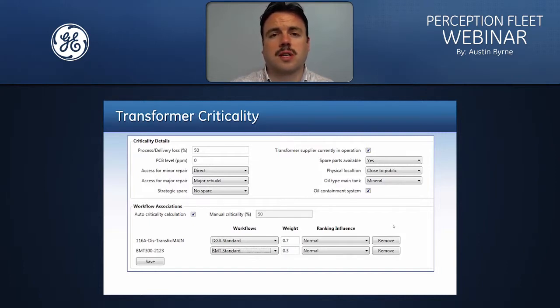So for example, if an asset is close to public and access for major repair is major rebuild, then that directly impacts the risk index categorization for that asset because it is seen as being at higher risk and a higher criticality. So a transformer with similar measurement characteristics as this particular asset will have a lower risk index because this asset is more critical in terms of the information fed into Perception.